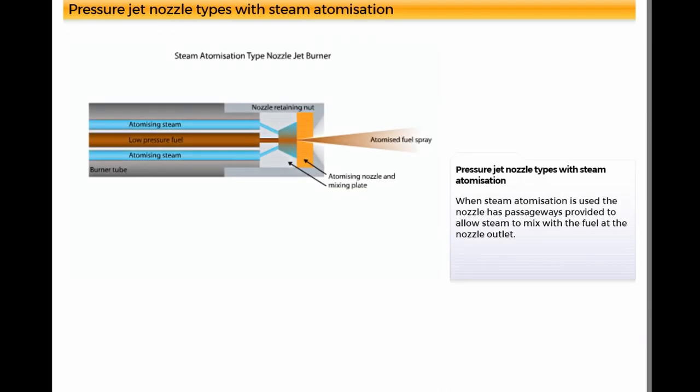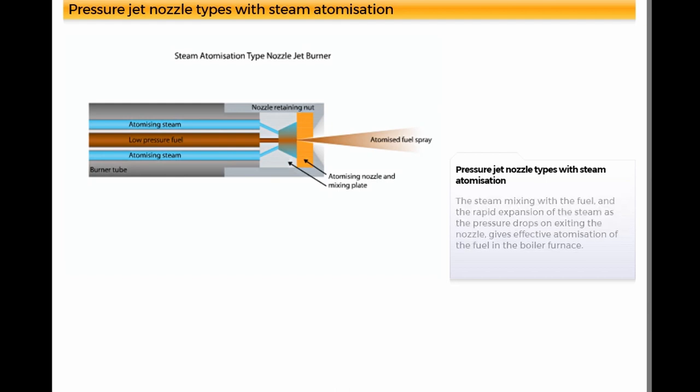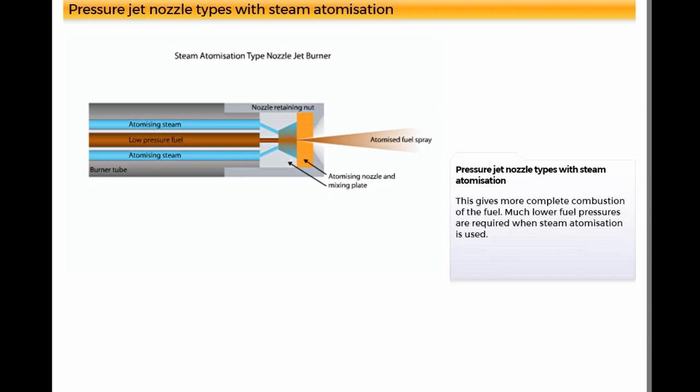When steam atomization is used, the nozzle has passageways provided to allow steam to mix with the fuel at the nozzle outlet. The steam mixing with the fuel and the rapid expansion of the steam as the pressure drops on exiting the nozzle gives effective atomization of the fuel in the boiler furnace. This gives more complete combustion of the fuel. Much lower fuel pressures are required when steam atomization is used.